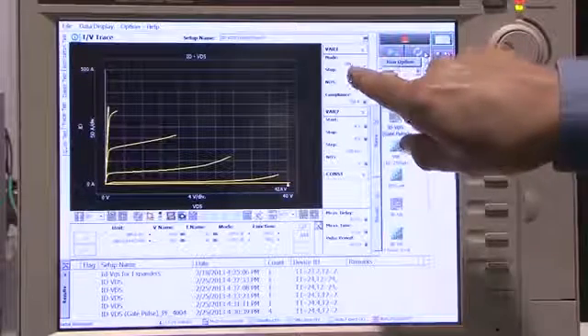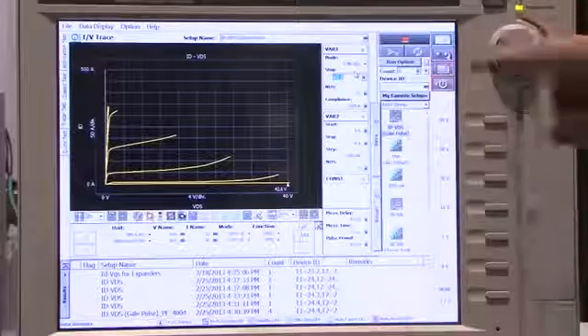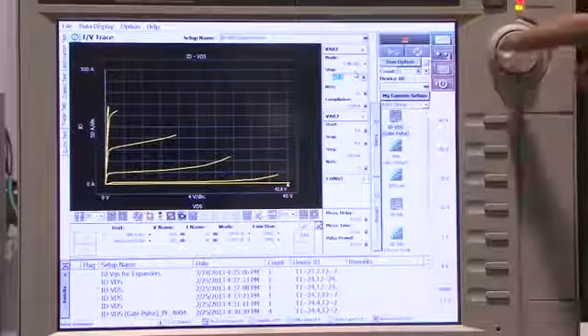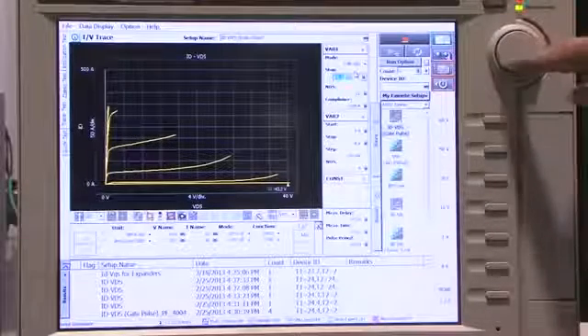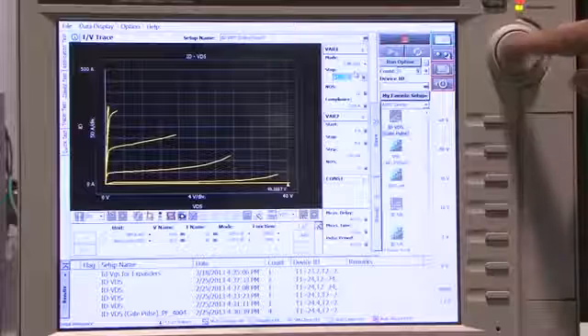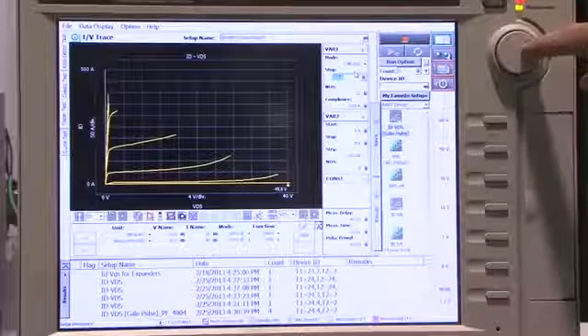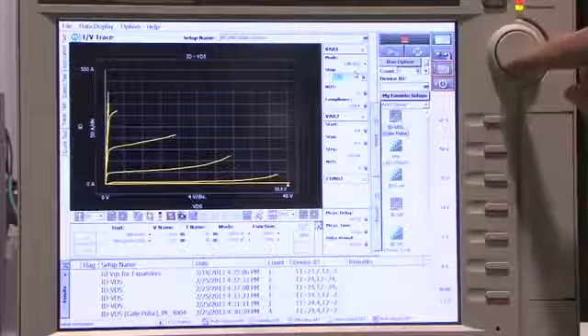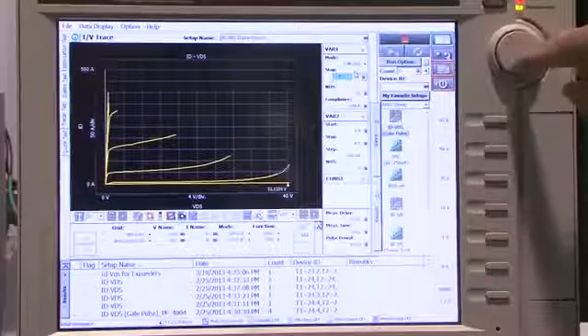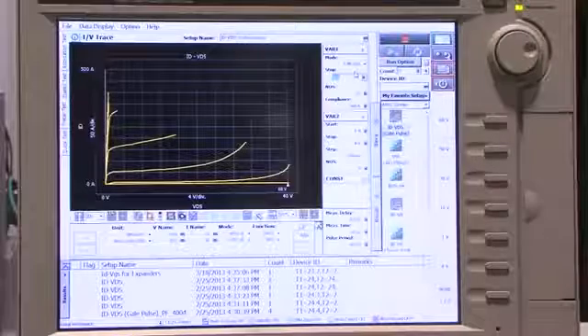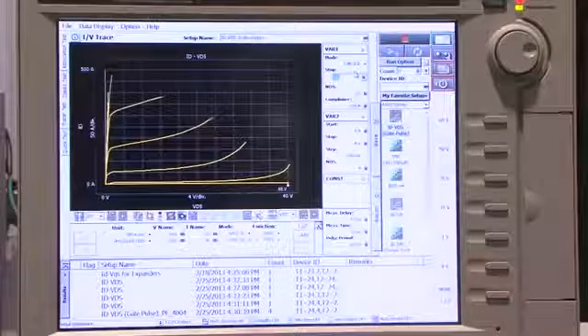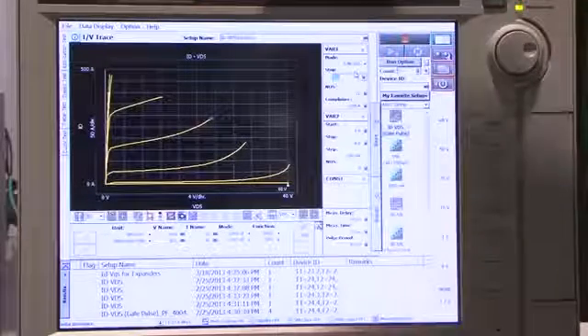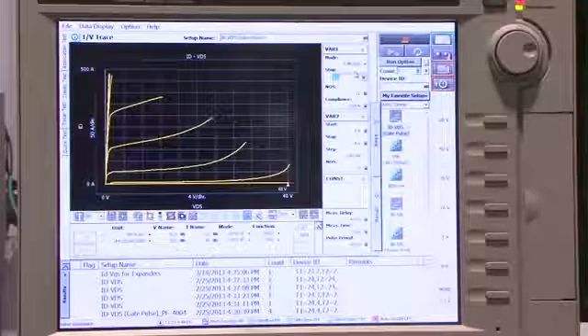Now I can actually go in here just like on a regular curve tracer and select it again. Notice this is a touch screen. So I can go ahead and start increasing the voltage. And as I increase the drain voltage here up to maximum, you're going to see that the curve changes. So now I'm actually testing up to 500 amps on the device.